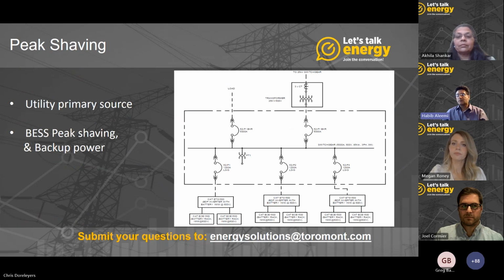In this application, the power system consists of utility and battery bank system. Utility is the primary source of power to energize the load. During a high demand or high peak time, the batteries could come online and take a certain amount of load for a certain amount of time, depending on how big the battery size is. When it's not peak time, the utility could recharge the batteries. Also in this application, if utility is not available, the batteries could energize the load for a certain amount of time. Again, it depends on how much load is available and how large the batteries are. In this application, we can see the battery banks are used for peak shaving and backup power. If we can go to the next slide, please.